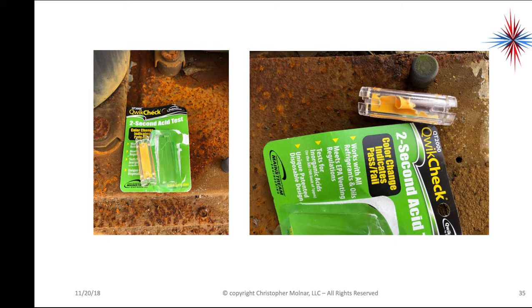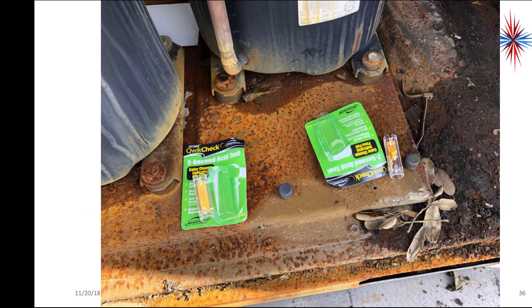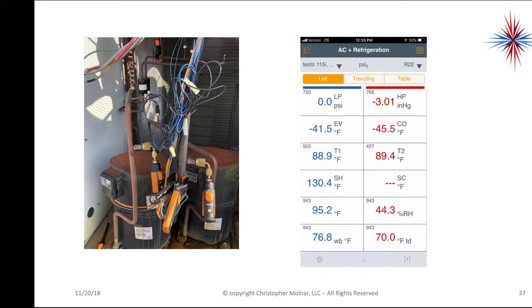We have two compressor circuits, had to do two at the same time. Both came back negative. Let it sit a while, still negative. Put my gauges on the first circuit. Okay, that's compressor 1. Now you'll remember compressor 1 and compressor 2, or Y1 and Y2, were jumped out. Okay, so compressor 1 has 0 psi of refrigerant in it. Okay, no refrigerant in that circuit whatsoever.